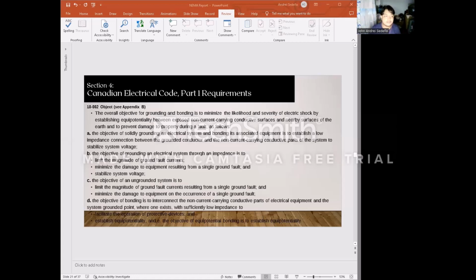Next is the objective of grounding an electrical system through an impedance: to limit the magnitude of ground fault currents, minimize the damage to equipment resulting from a single ground fault, and stabilize system voltage. The next is the objective of the ungrounded system: to limit the magnitude of ground fault currents resulting from a single ground fault and minimize the damage to equipment on the occurrence of a single ground fault.